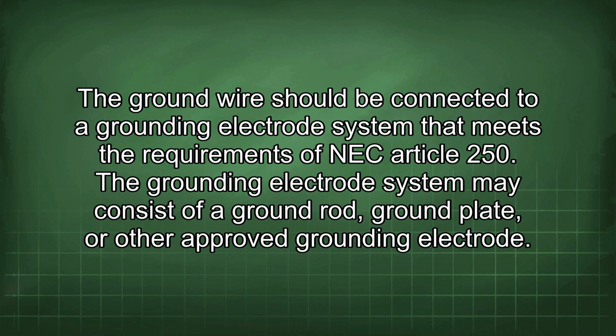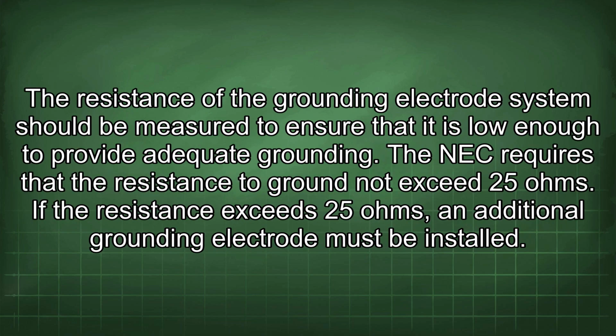The grounding electrode system may consist of a ground rod, ground plate, or other approved grounding electrode. The resistance of the grounding electrode system should be measured to ensure that it is low enough to provide adequate grounding. The NEC requires that the resistance to ground not exceed 25 ohms. If the resistance exceeds 25 ohms, an additional grounding electrode must be installed.